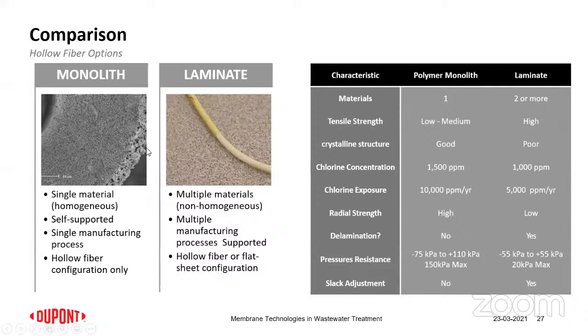The problem you would generally see in these systems is that laminates are more vulnerable to damage. They can peel off. Of course, they talk about higher strength. The braided support structure has higher strength, but when the filtering layer gets removed, the braid remains only as a support structure without proper resistance for filtration, whereby the main purpose of filtration, achieving the filtrate quality, is compromised.